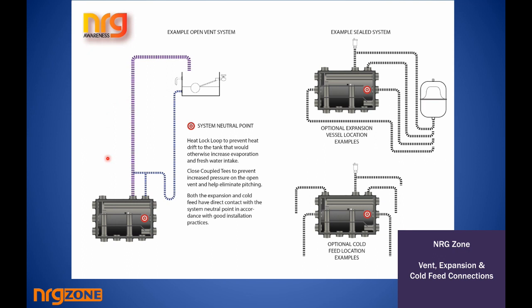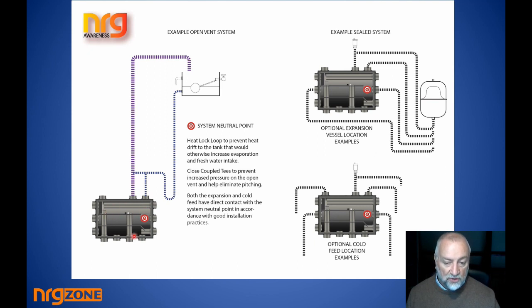So a critical point of system design is where the expansion or pressure vessel is located and where the cold feed is located. So we're looking at three things here. We're talking about the way we would go about a combined expansion, or not combined as such, but a way to use the cold feed that is independent with a connection to expansion. We're talking about pressure vessel location, and we're talking about cold feed location. The target for all connections to open to atmosphere points is the system neutral point. We've already said that the perfect system neutral point, you can't get any better, is where the pumps draw from and the system is collecting the heat and where both of those meet, but also then of course where you bring in your cold feed.